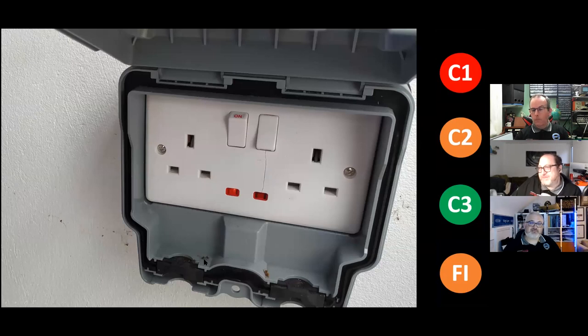Right, here's a nice, quick, simple one. Wonderful weatherproof sockets that we find everywhere, with a very simple visual inspection observation, because we inspect before we test. What do we think? I quite like that socket because it's a changeable one. It's BG, by the way. Is it? I hate it immediately, and I'll give you a million reasons why. The insulation resistance for the LEDs in series is a pain.